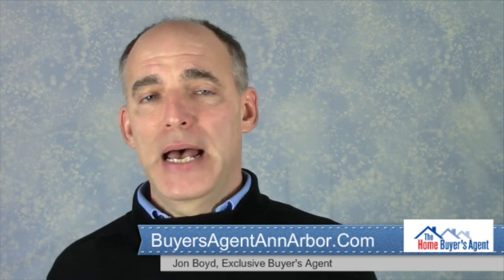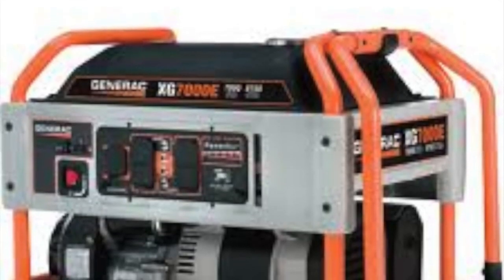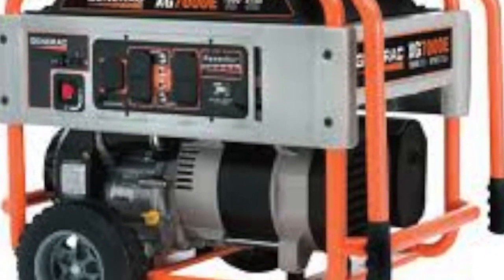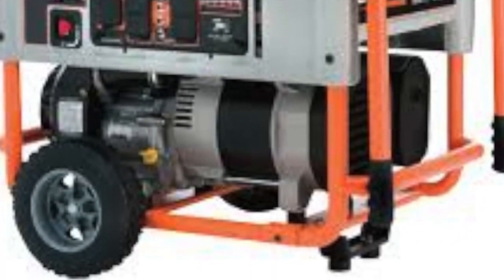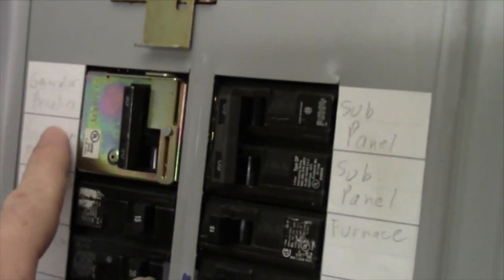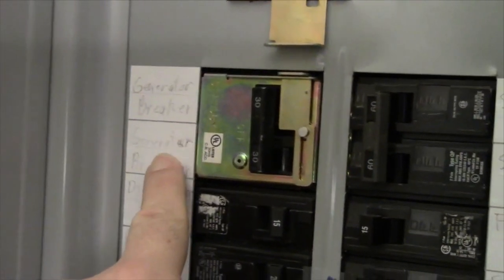The first, the basic interlock systems, can be very modest in cost, but they do normally take professional installation. They also allow you to use different portable generators for backup power. Portable generators usually use gasoline for fuel, and the inconvenience is that somebody has to watch the amount of gas in the tank, and it is a bit smelly and dangerous to refuel. The minimum size for a generator for this use is normally based on the power requirements of the well pump, the furnace of the home, the refrigerator, freezers, that type of thing. 7,000 watts is a typical power range for these systems. They usually have a single large switch that switches the home power from the utility company to the generator, or as an alternative they may use a physical interlock that won't allow the generator to energize the home unless the utility company breaker is switched off.